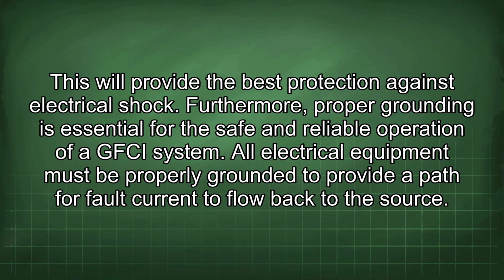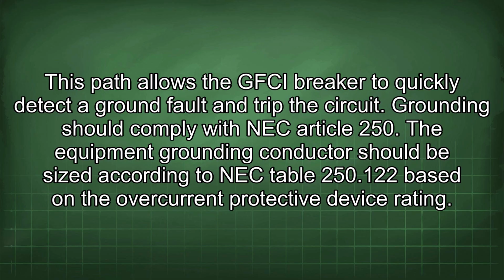Furthermore, proper grounding is essential for the safe and reliable operation of a GFCI system. All electrical equipment must be properly grounded to provide a path for fault current to flow back to the source. This path allows the GFCI breaker to quickly detect a ground fault and trip the circuit. Grounding should comply with NEC Article 250. The equipment grounding conductor should be sized according to NEC Table 250.122 based on the overcurrent protective device rating.